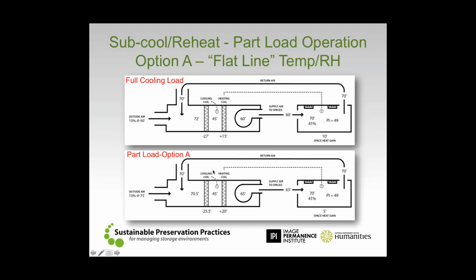Well, that system in a part load scenario, if it's still trying to achieve that particular temperature and relative humidity goal, here's what's going to happen. You bring in the cooler air, you mix it with return air. So now we've got cooler air going into the cooling coil, which means that we have to do a little bit less work at the cooling coil. That's good news, right? We're not using as much energy as we did up here. The bad news is that because it's not as hot outside, there's not as much heat gain in the room, right? We had 10 degrees on a 90-degree day, but only 5 degrees on the 75-degree day. And that means that if we only have 5 degrees of heat gain in the space, we don't have to send the air in as cold as we did in the past, right? We needed to send it in at 60 degrees on a 90-degree day. On that 75-degree day, maybe we only need 65 degrees. What happens then is if we still do that same amount of work here at the cooling coil to achieve that dew point, guess what?